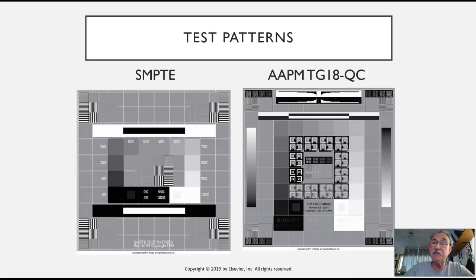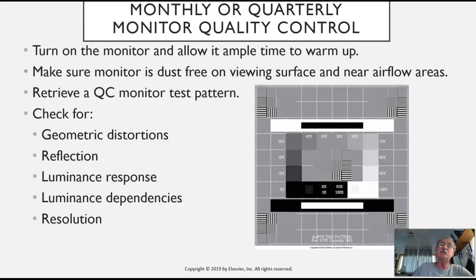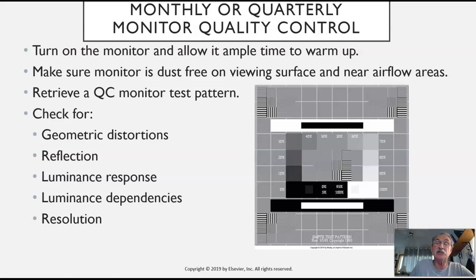The AAPM pattern is laid out a little differently but you can achieve the same kinds of readings from it. You turn on the monitor and allow it to warm up, make sure the monitor is dust free on the viewing surface and near the airflow areas, then bring up one of these test patterns and check for geometric distortions — straight lines should appear straight and not curved. You'll look for reflection, luminance response, luminance dependencies, and the resolution of the monitor, because the monitor is how we see our X-ray images.